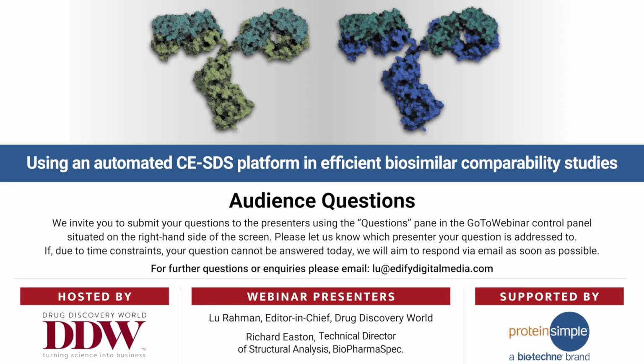You mentioned loading samples and reagents, but what does this actually entail? All reagents associated with the Maurice system come ready to use from Protein Simple. So it's just a case of transferring reagents from a bottle to a vial. It's very quick and simple, and gives you high reproducibility because you can have faith in the reagents, and the automation process is very quick to load, to set the system up, and to get everything operational and running.